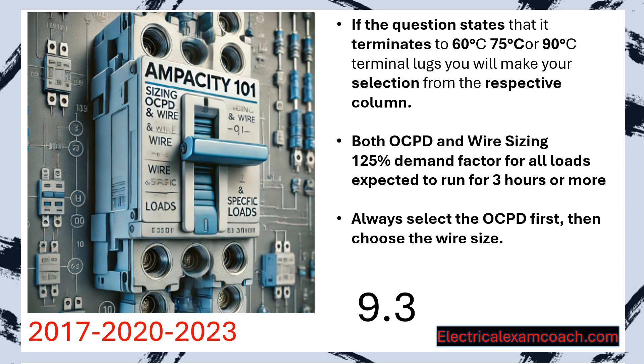If the question states that it's terminating to 60, 75, or 90 degrees C terminal lugs, you're going to make your selection from that respective column under normal circumstances. With both OCPD and wire sizing, we still have that 125% demand factor for all loads that are expected to run for three or more hours. We will always select the overcurrent protective device first and then choose our wire size — it will make more sense why we do that once we start sizing services in the next lesson and larger amperage questions like a thousand amps or greater.